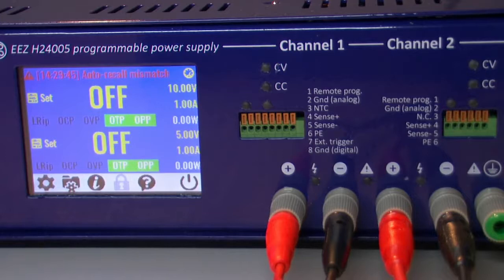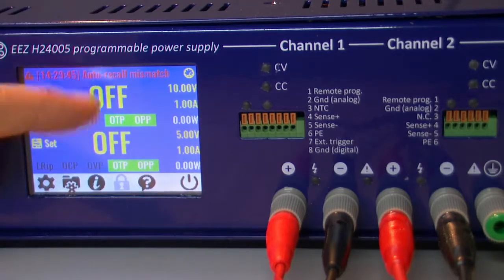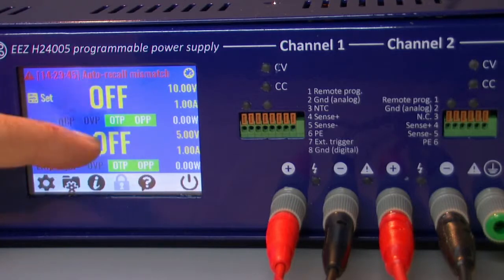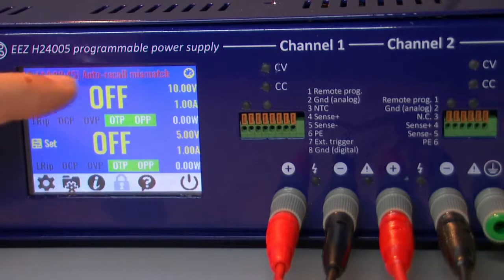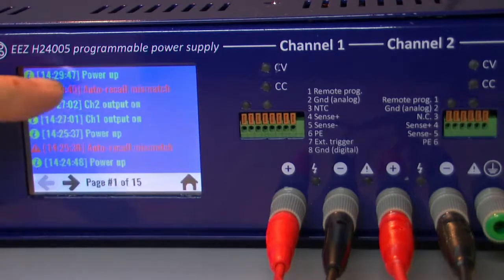Good. Thanks to that security mechanism, firmware on the startup recognized a difference between the last set value and the values stored in the power up profile. And put both channels in off, output is off. And we'll get that auto-recall mismatch information in our log file.